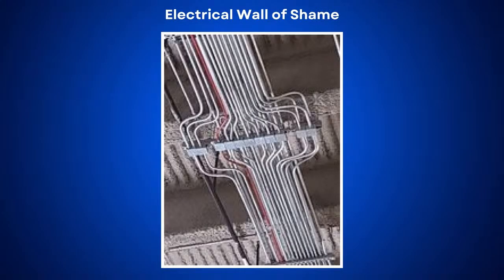Oh, this one's a good one. This was actually last week's Myth of the Week, stolen from the Wall of Shame group, and a guy said, we just found this. And instantly, right away, you're looking at the no more than 4 quarter bends between pull points. And you're looking at the securing and supporting within 3 foot from a box enclosure. Oh yeah, that's the first thing that came to my head right when I saw it.